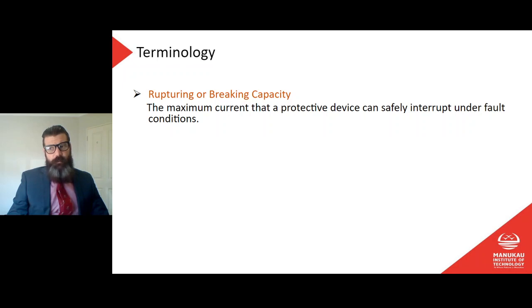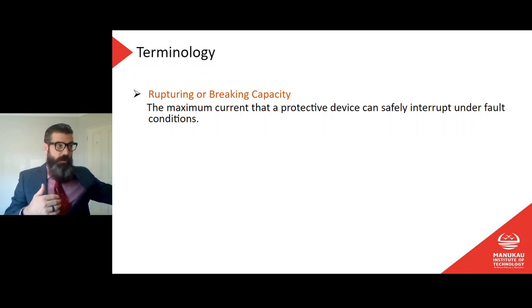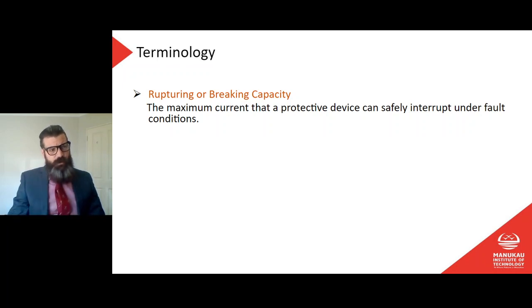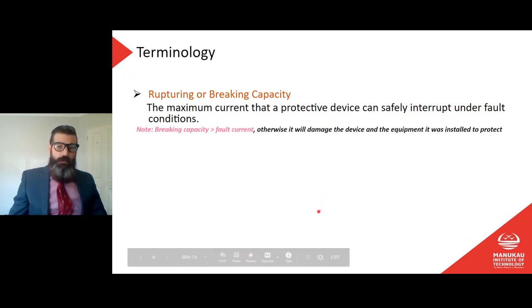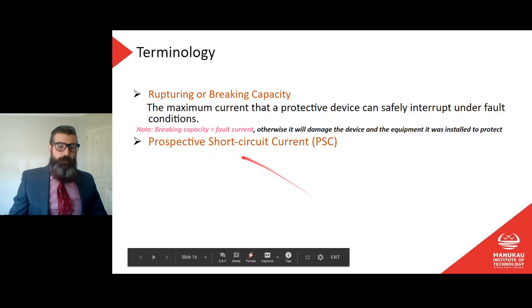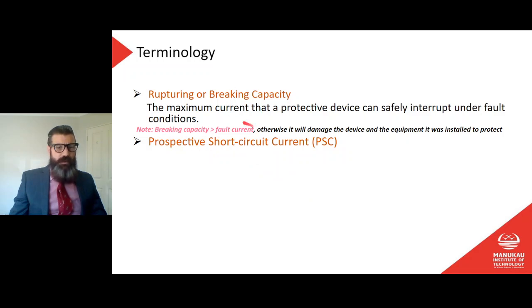You will from time to time, if you're in a big factory that has really large supply cables, maybe even its own transformer, it's possible to get very, very high short circuit currents because they have very, very low loop impedance, right? It's a very, very low resistance between the switchboard or sockets or whatever going back to the source of supply, the transformer. And as that impedance goes down, the prospective short circuit current goes up. So we need to know what that short circuit current will be, and we need to make sure our breaking capacity of our circuit breakers is exceeding that short circuit current. There we go. That breaking capacity must be greater than the fault current.